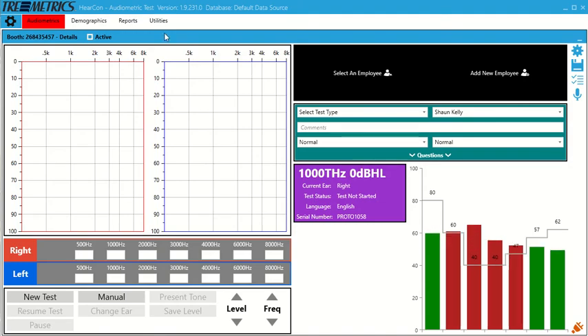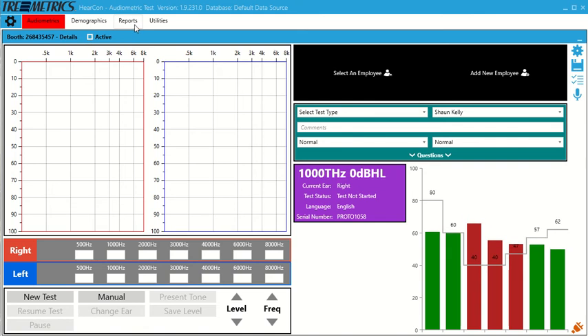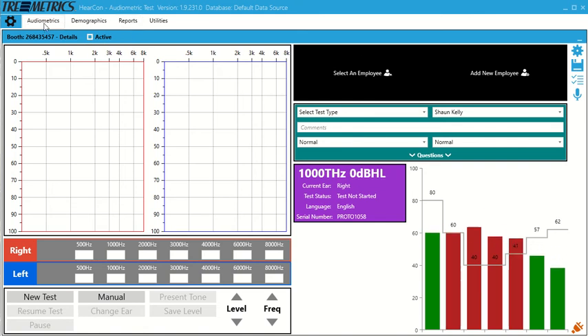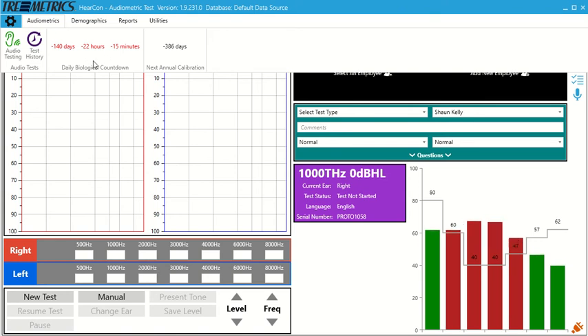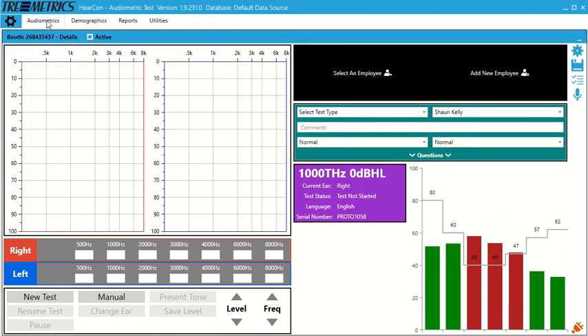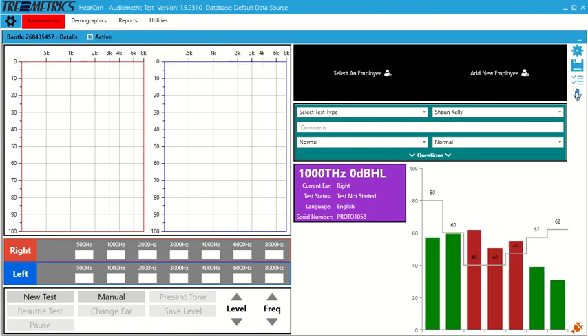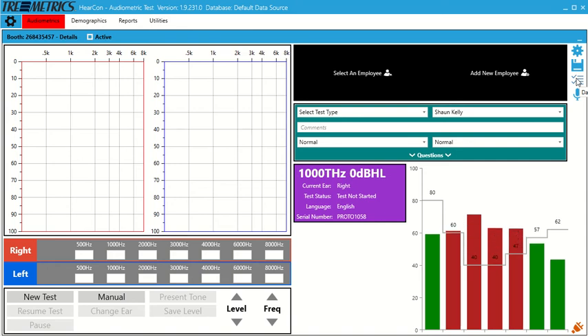So this is the HearCon software. This software is included with the audiometer. If we look at audiometrics here, we see it's color red. If we click on it, you can see there's a countdown for your daily biological. So we can go over here, daily checks, start daily biological.